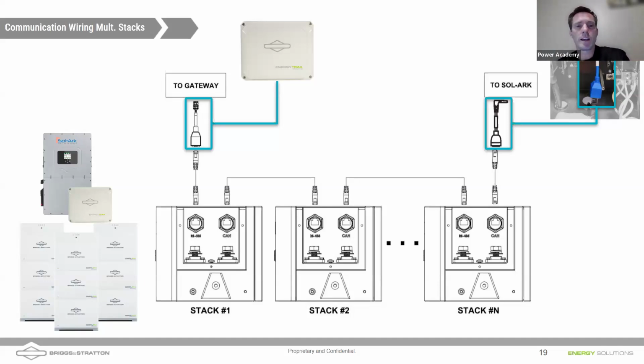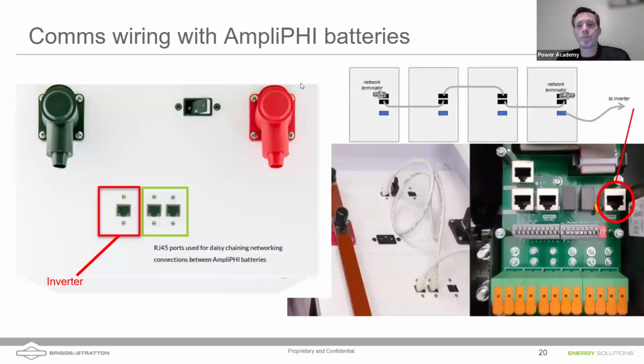So use Cat5 or Cat6 graded cable, but we recommend using the shielded type, the shielded twisted pairs, especially if you're running these in conduit, which have other AC power running through them. With the AmpliPHI batteries, the wiring's very similar. No dongle for this one, it goes straight out of the inverter port on the batteries.